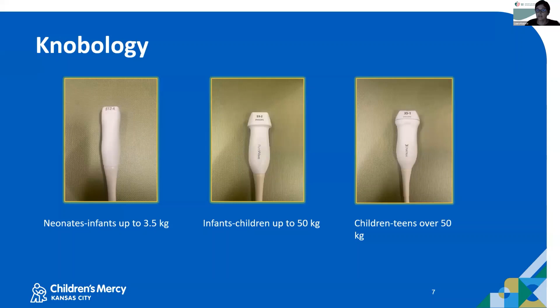So every probe, we've chosen the S9 here at the top, is going to have a preset. And the preset, you can have a factory setting, which is what the machine manufacturer decides. This looks good. This is where we think it's a great place for you to start. If you're lucky, your institution is going to have their own preset that they have adjusted the depth, the 2D settings, the color, and the Doppler settings. So it's a really great place to start.